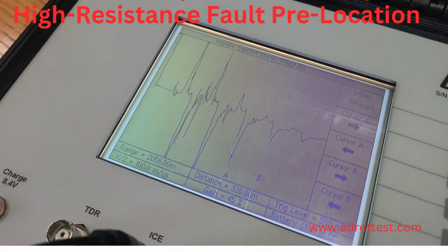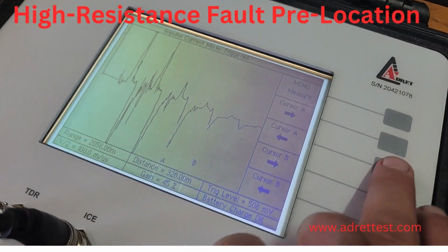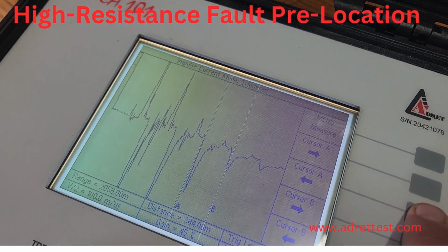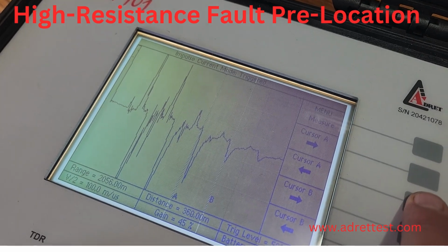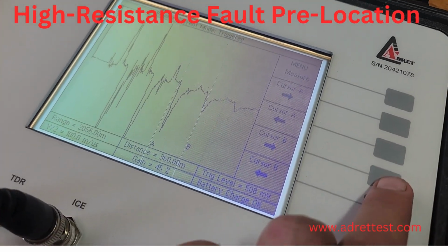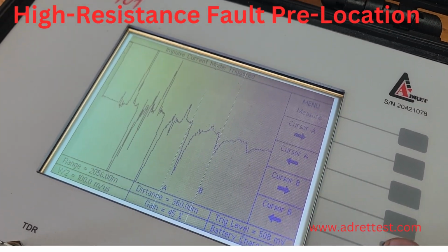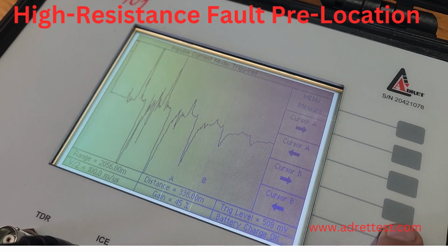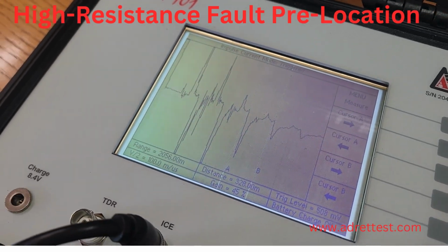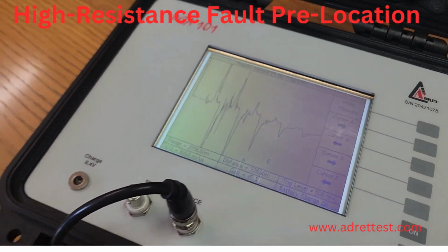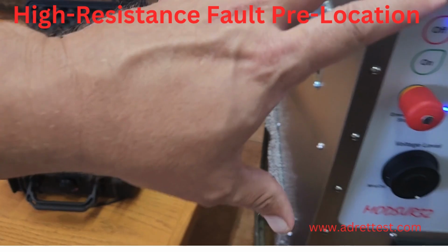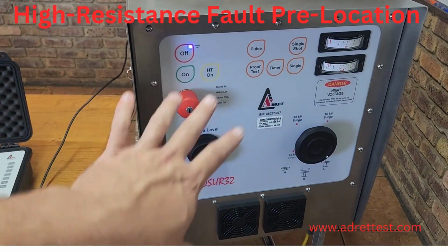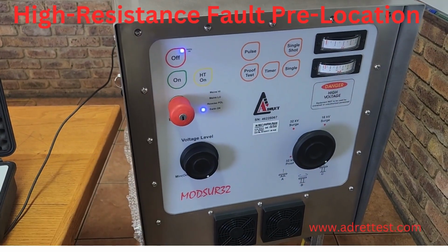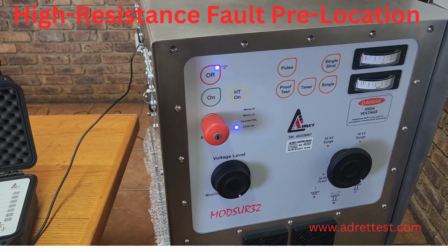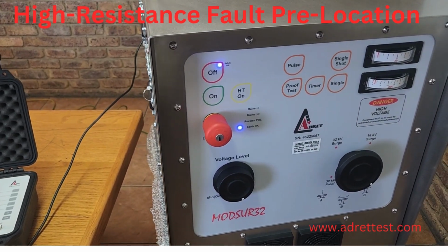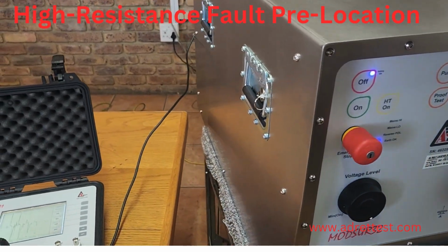Alright, you can also put it on where it starts to go down, and there again, 328. Rule of thumb is round about between 28 and 30 meters of cabling inside the machine. And so if you deduct that, you will be on your 300 meter fault.